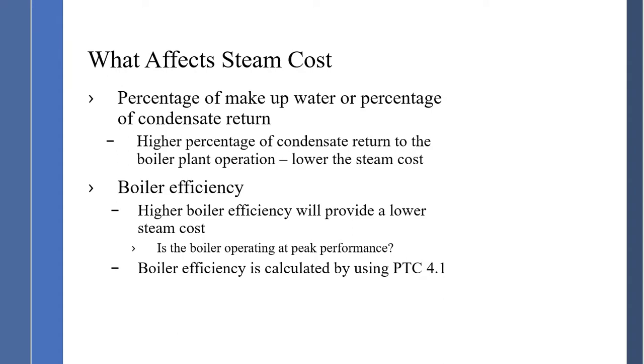What affects steam costs? Percentage of makeup water and percentage of condensate return — higher percentage of condensate return to the boiler operation will lower the steam cost. Last, boiler efficiency: higher boiler efficiency will provide a lower steam cost. Is the boiler operating at peak performance? Boiler efficiency is calculated using PTC 4.1 and should be monitored daily.